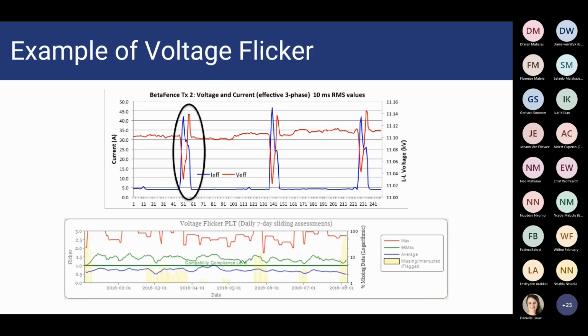Here's an example of a voltage flicker problem at a specific site. We can see the current, the blue line, compared to the line-to-line voltage, which is the red line. We can see the sudden increase in the RMS current at specific times, and that causes a rapid change in your voltage magnitude. You can see the voltage magnitude dips, and that variation leads to voltage flicker. For this specific site, if we do an assessment over a longer period of time, we can see that the maximum 95th percentile long-term flicker, the green graph, is above the 1 per unit level specified in NRS 048.